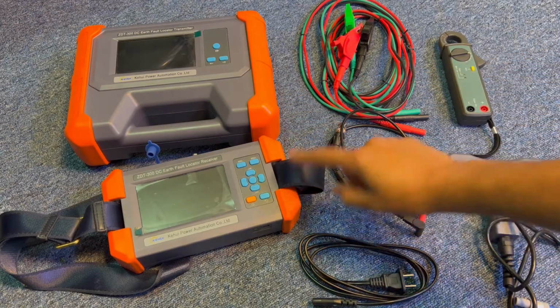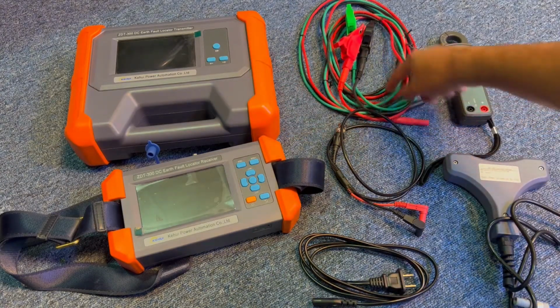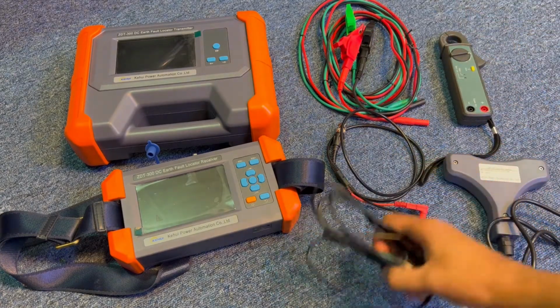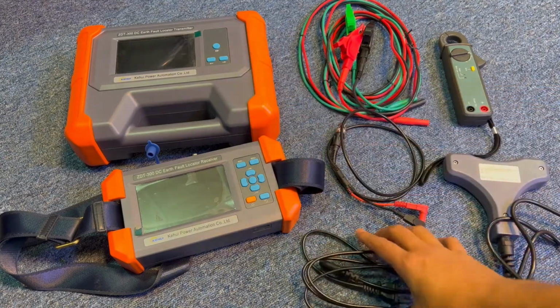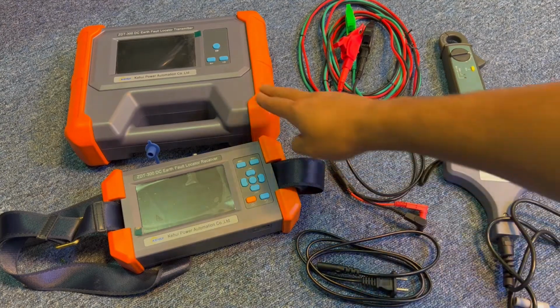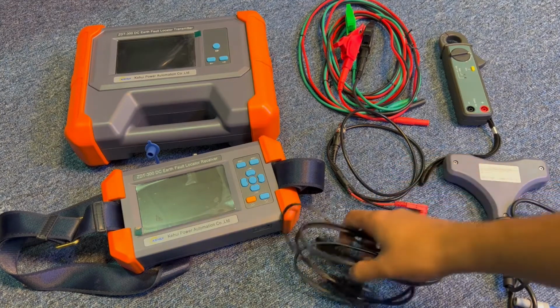You can see here a transmitter unit, a receiver unit, and a cable which connects to the main DC-DB system through the transmitter, and goes to the main positive, negative and the ground. Then you have a power cable here which is used to power the transmitter when you are using it below a 110 volt DC system. This system gets energized automatically when you connect to a 110 volt and above DC system. But if you are using a voltage lower than 110 volt, then you need to give an additional AC power supply to this transmitter.